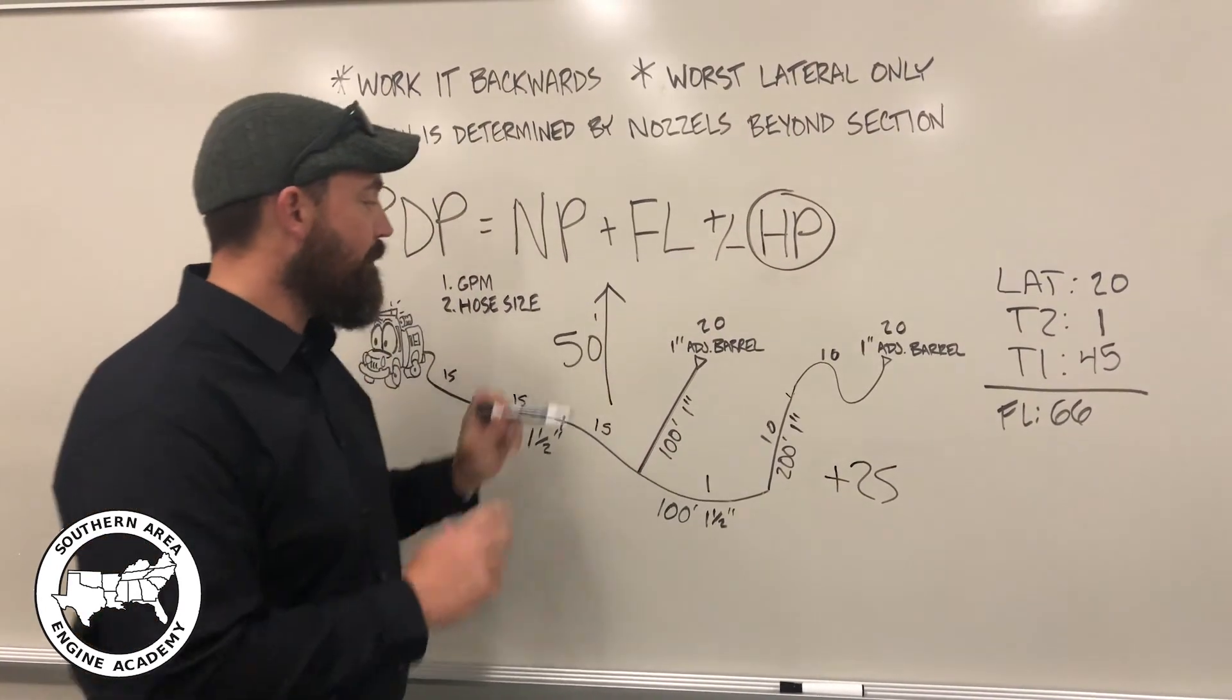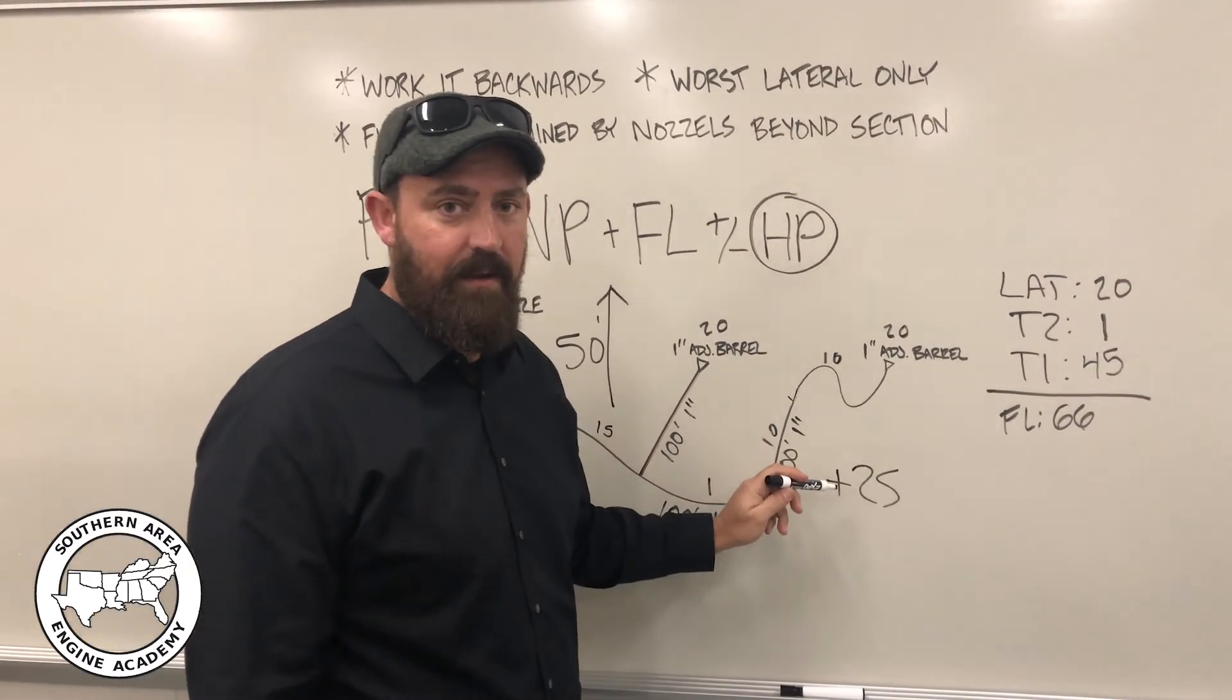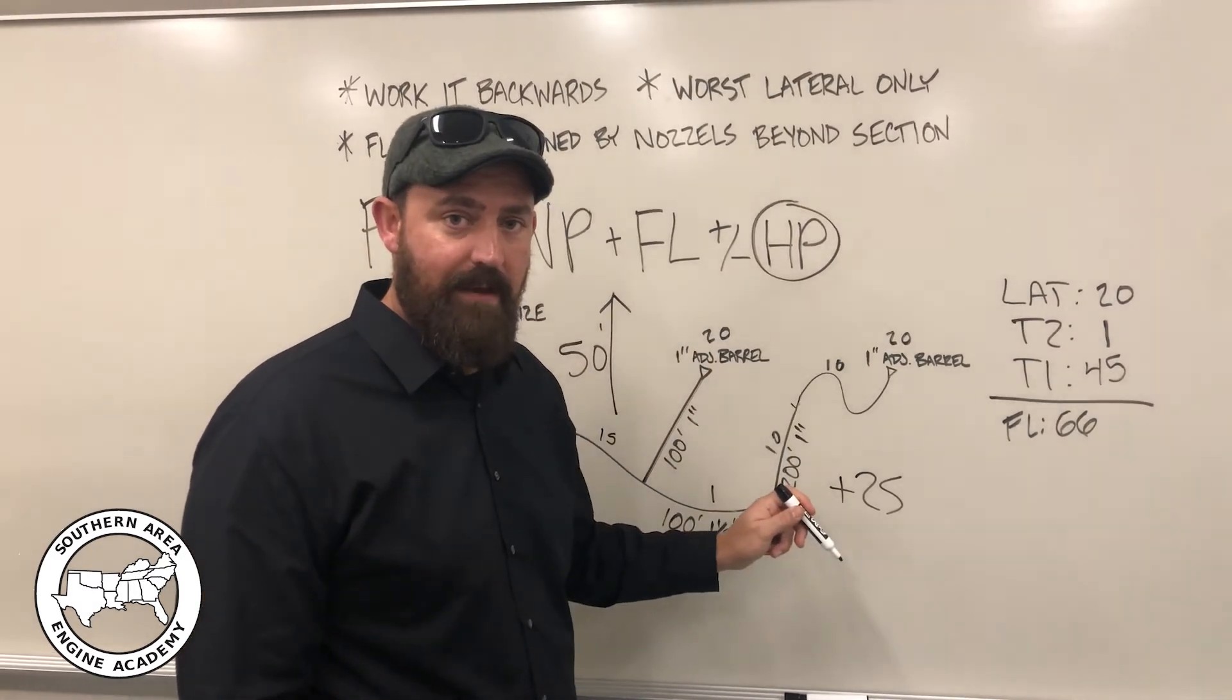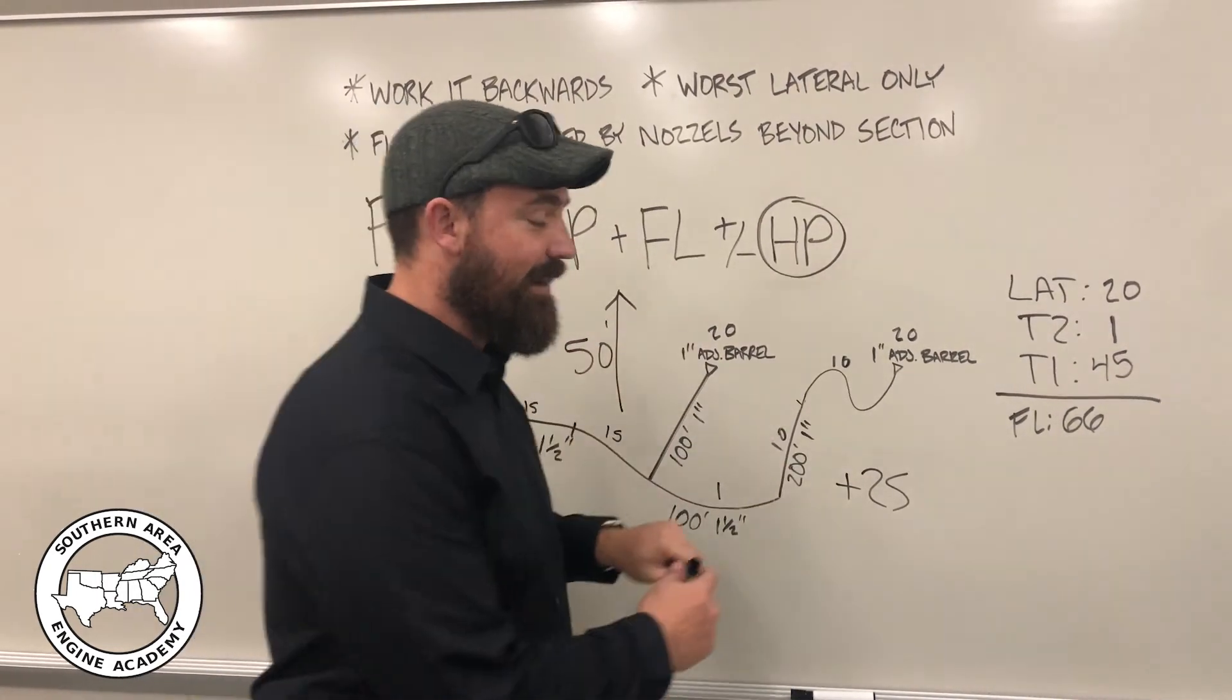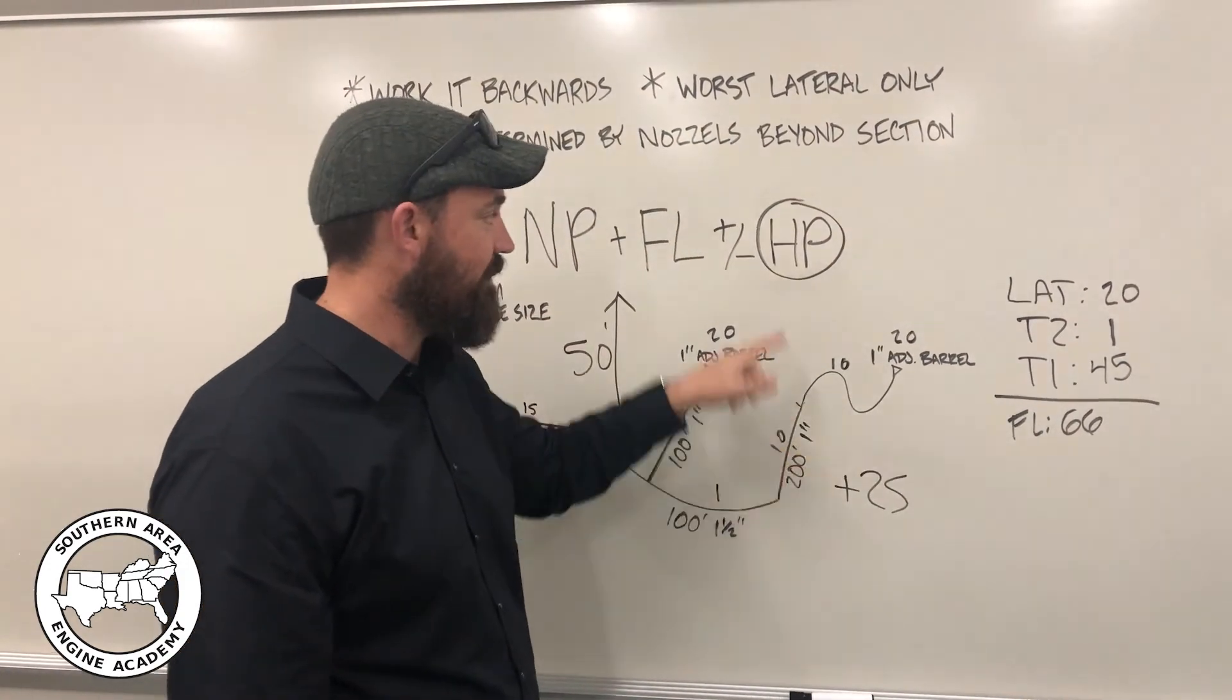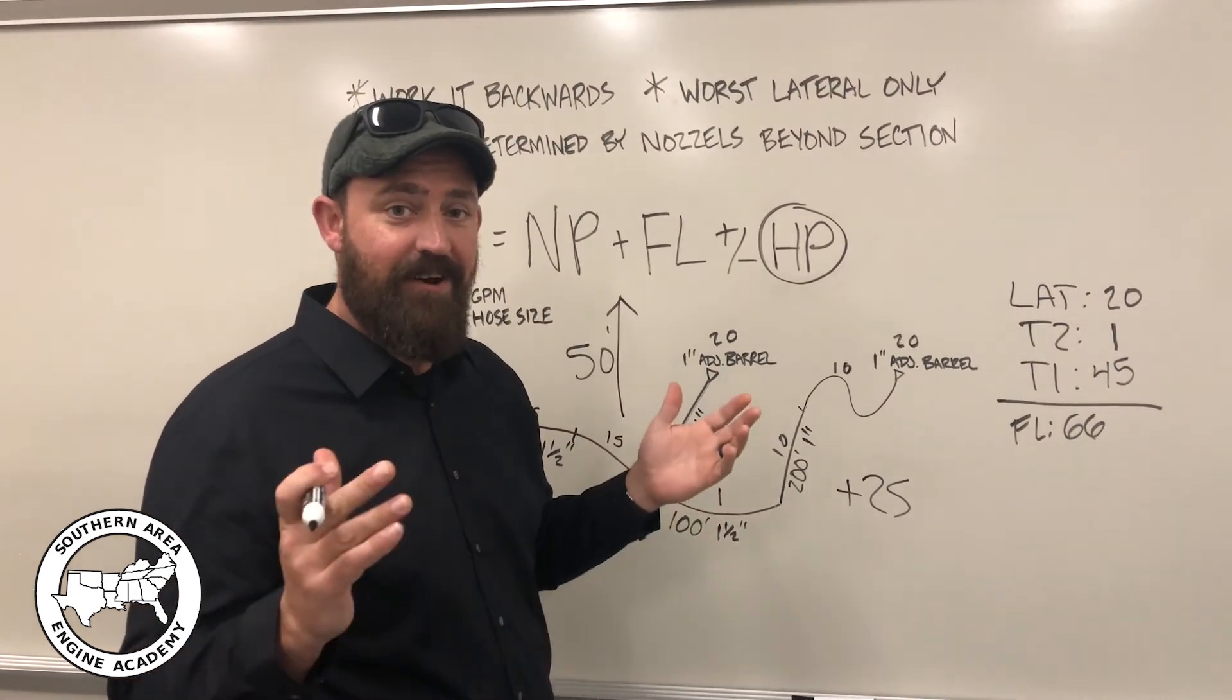Now, if the opposite were true, if this were going 50 feet downhill, we would have to subtract 25 pounds because we'd be picking it up as that water moved its way downhill. So, it's pretty simple, two to one, we'll just remember when it's going downhill to subtract and not add. So, in this case, we need to add 25 pounds. That will be the HP portion of the formula. And now all we have left is putting it all together.